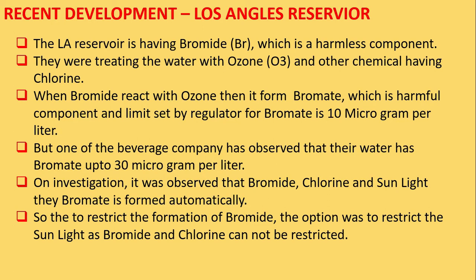The limit set for bromate is up to 10 micrograms per litre. One day, a beverage company observed their water bromate level was up to 30 micrograms per litre and complained to the water supplier. On investigation, the water supplier found that bromide and chlorine from cleaning agents of the water treatment plant, combined with sunlight, were forming bromate automatically, sometimes going beyond the permissible limit. The only solution was to reduce the bromide, chlorine, or sunlight. Since reducing bromide and chlorine was not possible, they decided to restrict the sunlight.